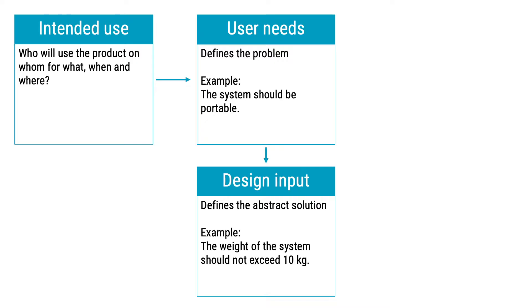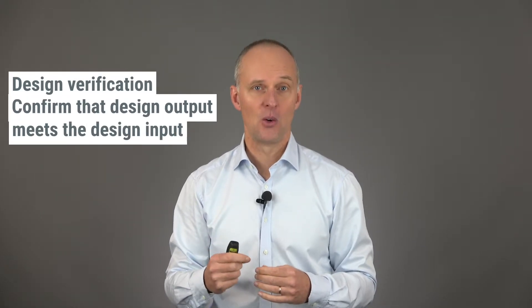The regulatory requirements do not say who should come up with the user needs and design inputs. Many times the people competent to define user needs are found in management, marketing, or product management. Since design inputs should be technical in nature, they are usually established by engineering and should use engineering language. When you have designed the product, you should check that the design you came up with actually meets the requirements you defined at the beginning — this is a general principle in product development and in the medical device industry it is also a regulatory requirement.